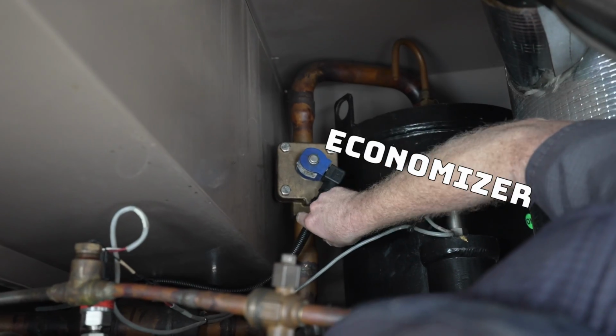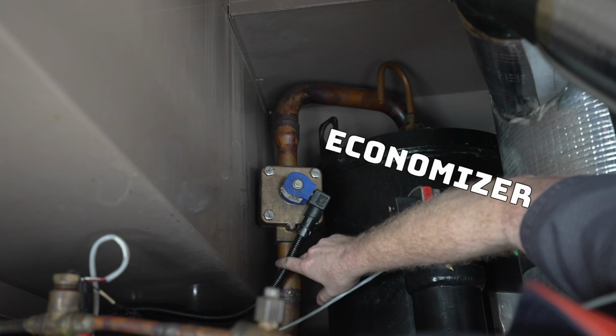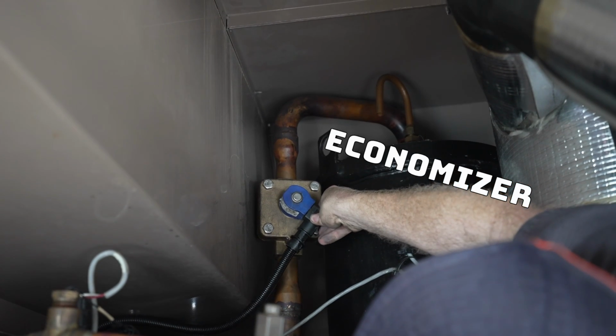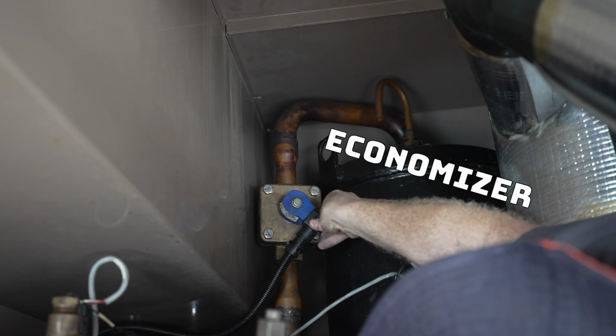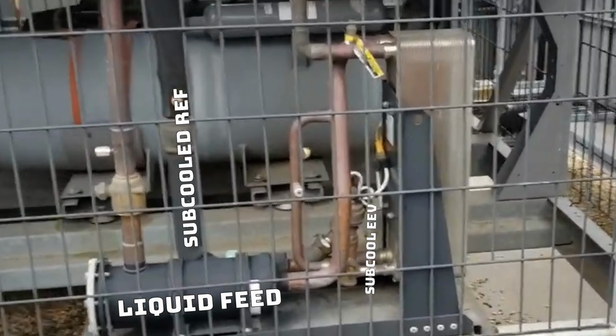So an economizer on a chiller helps us increase efficiency by how we manipulate the refrigerant. So instead of trying to bring, say, outside air in for free cooling or dehumidification of the space, instead we're going to use typically the refrigerant itself and its attributes to economize itself. There's two main ways that we do that inside of the industry. There's direct cooling, which is quite literally taking just a little bit of the liquid refrigerant that we're already running through the liquid line. We're going to flash a little bit of that through a metering device, and then we're going to pre-cool some of the liquid refrigerant before it gets to the evaporator.